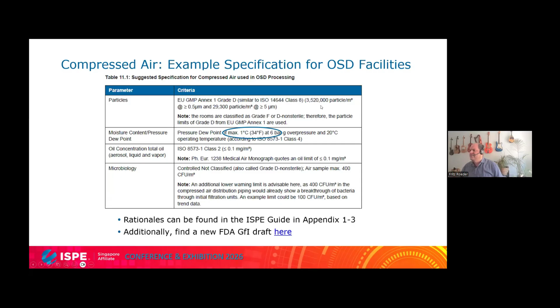Last but not least, oil. Many people used class 2 in the past. We chose this as well. It makes sense. Do not choose class 1 because the LOD of the measurements is typically higher, so you can't measure class 1 properly. Even with very specific Draeger tubes, it's tough to really measure and comply with class 1. So the first one was for chemicals, API sites, and OSD sites, tablets, capsules, and so on. And I would choose this one also for ointments and non-sterile liquids.